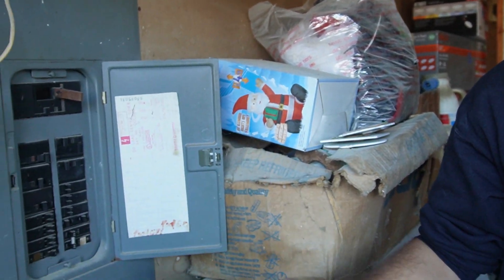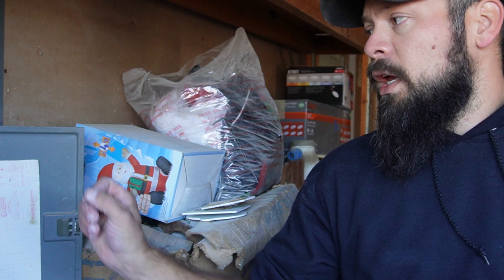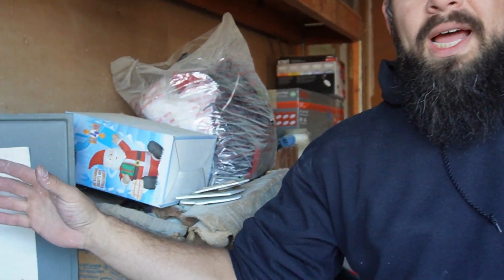A lot of people have asked us about a generator system. Do not hire a handyman to install a generator tied into your main breaker panel. What can happen is if you tie this in incorrectly and a utility worker — say from Oncor or one of the power supply companies — is actually working on the system while you have a generator kicked on, and you do not have the emergency shutoff disconnect to the main power supply, you can actually send a surge back onto the main circuit, back onto the power lines, and actually endanger or risk their safety.